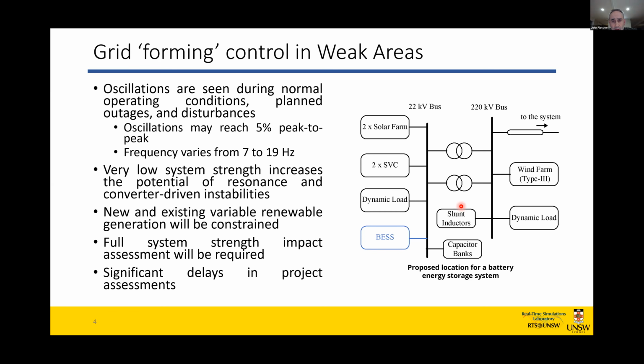But at the end of this line, you can see that there are a number of installations. There's a couple of solar farms, there's a wind farm, and all of this is out there to supply mining loads as an example. And this particular part of the grid suffers from an oscillation in the voltage, which can be up to 5%, with a frequency that varies somewhere between 7 and 19 hertz. So it's a real problem for that part of the network.